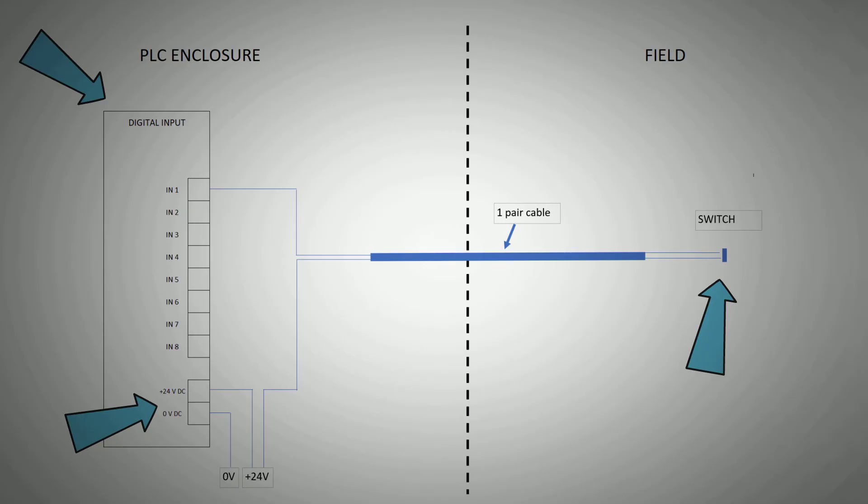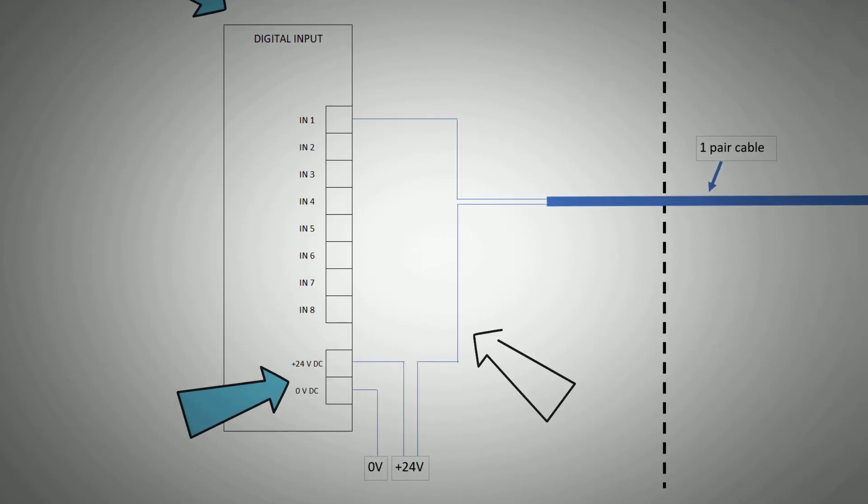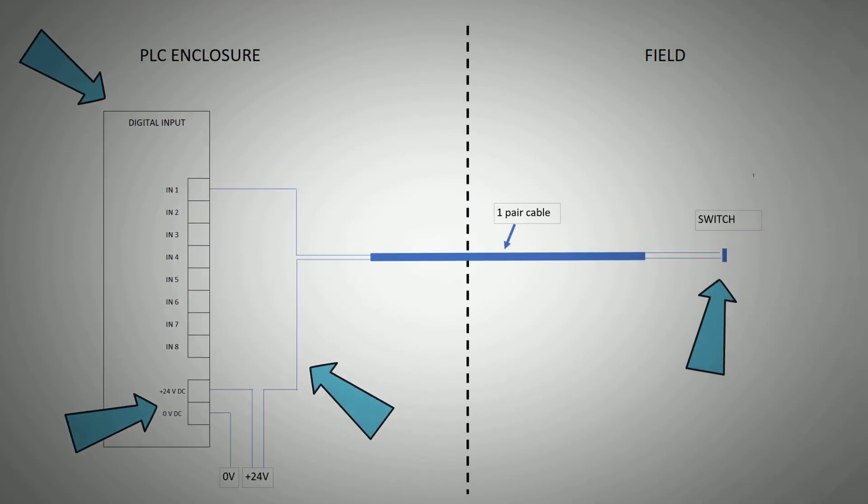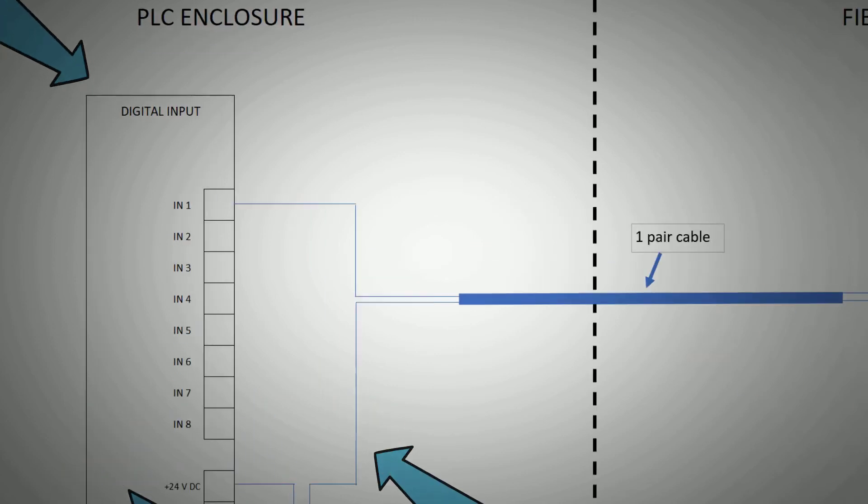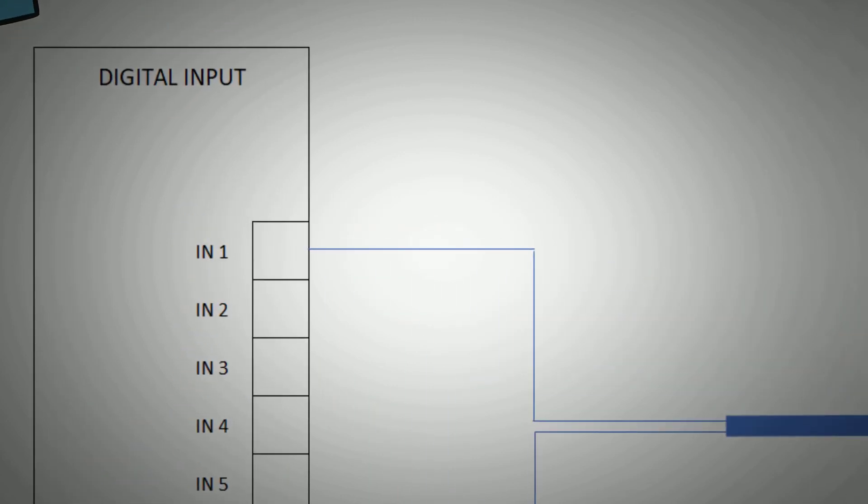We will then run 24 volts from the same source as our digital input card supply down one of the wires, through the device, and back on the other pair and connect through internal patch wiring into our input card.